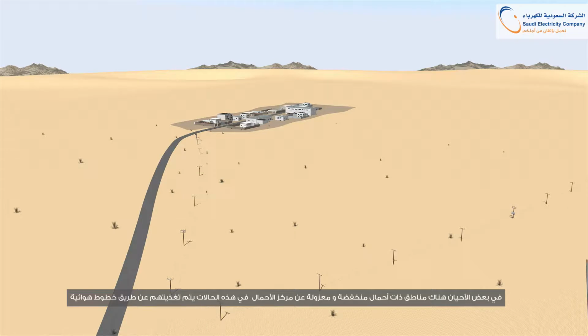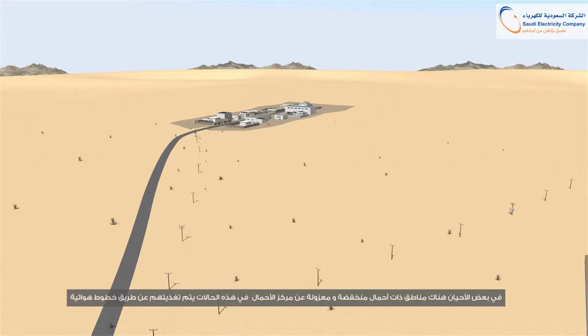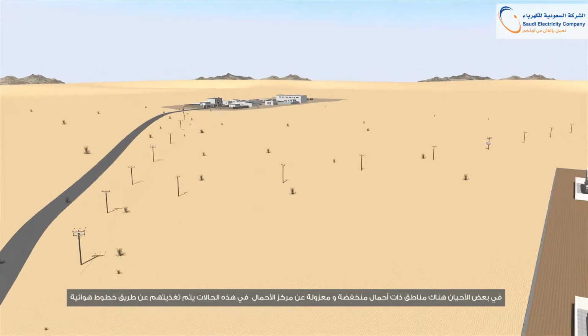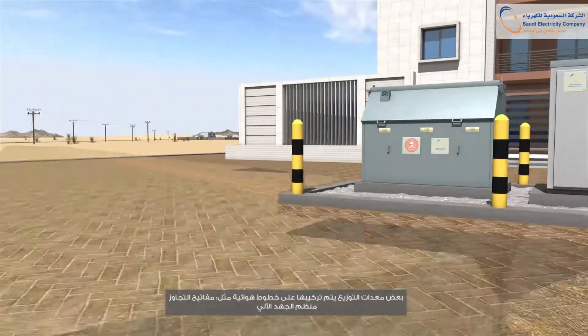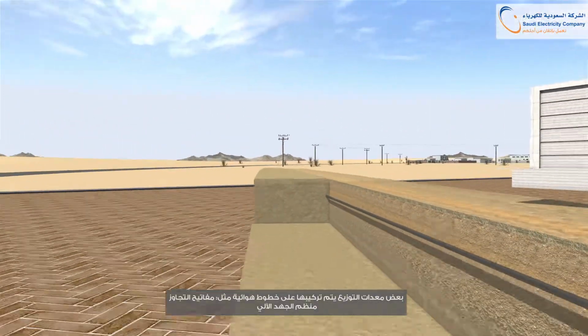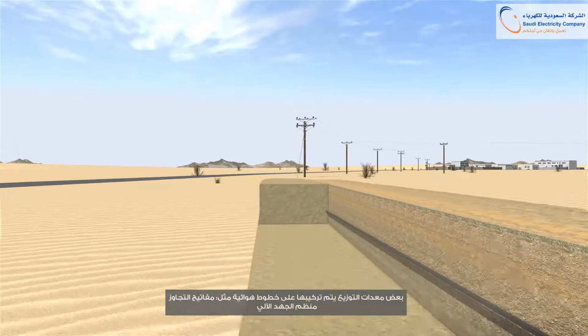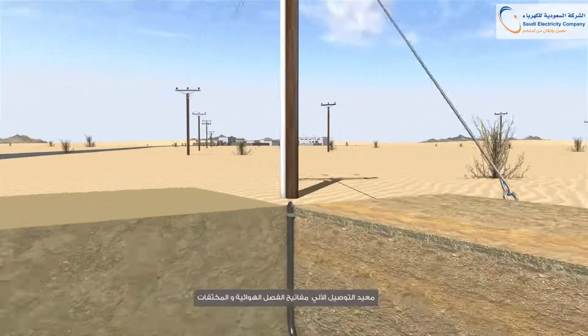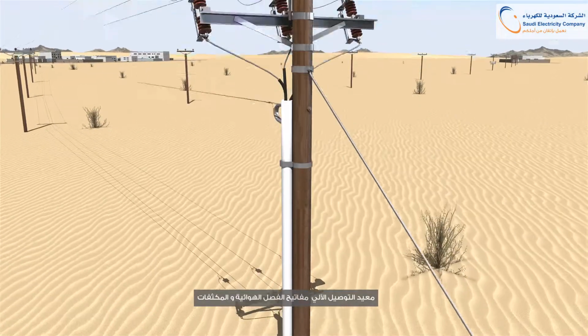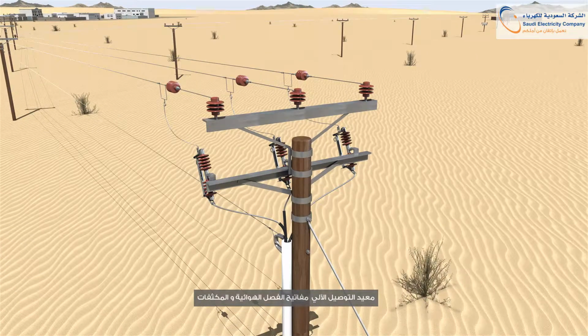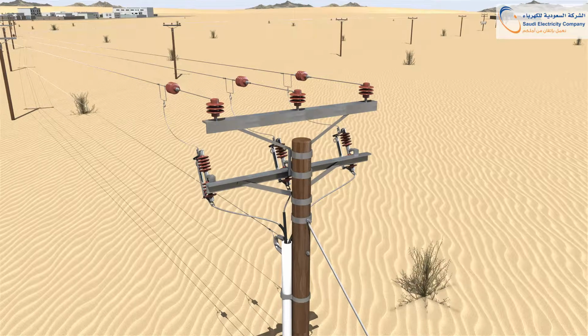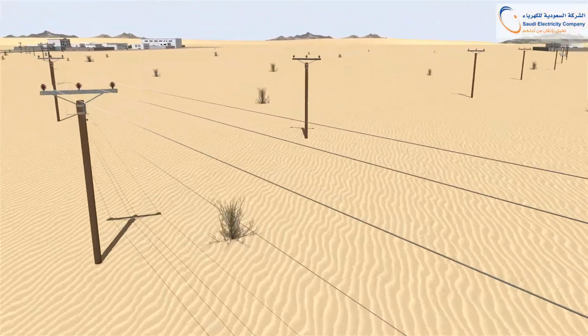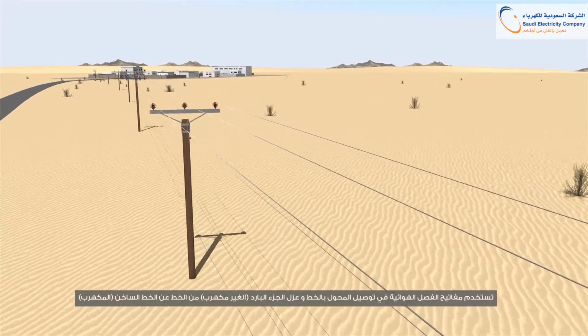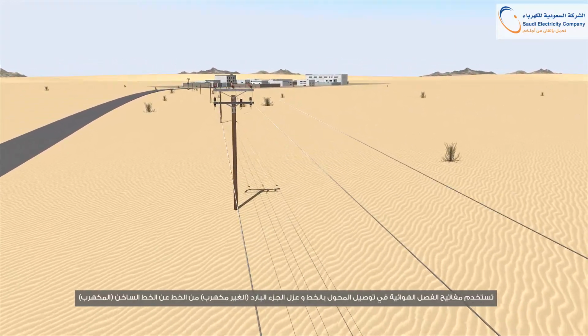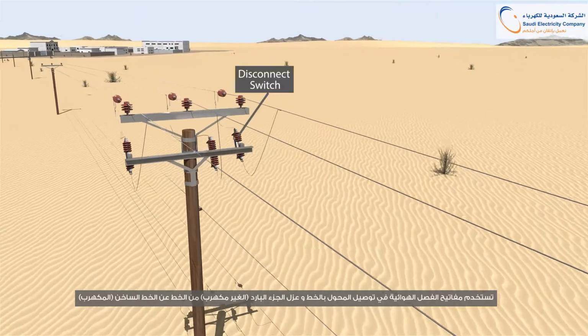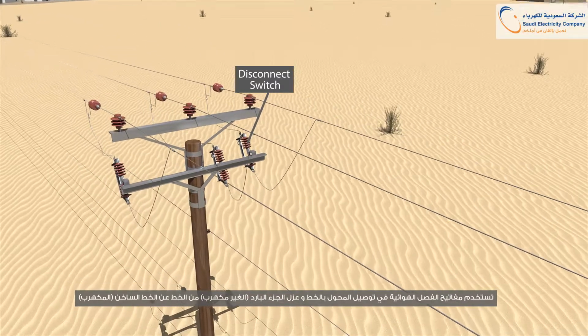Sometimes there are areas with low loads and isolated from the load center. In these cases, they are fed by overhead lines. There is some distribution equipment installed onto the overhead lines, such as disconnect switches, automatic circuit reclosers, automatic voltage regulators, bypass switches, and capacitors. Disconnect switches are used to connect the transformer to the line and isolate a dead section of the line from a live line.